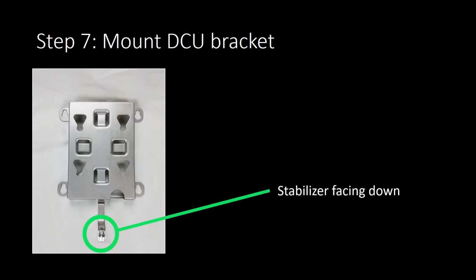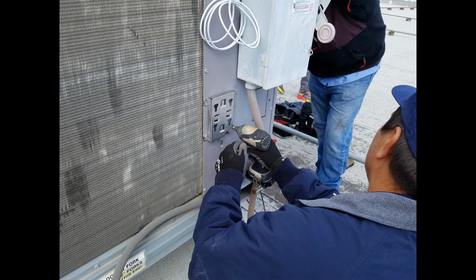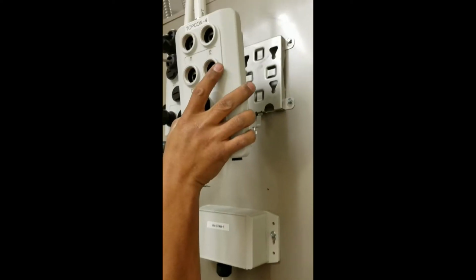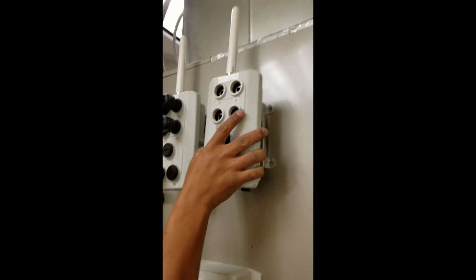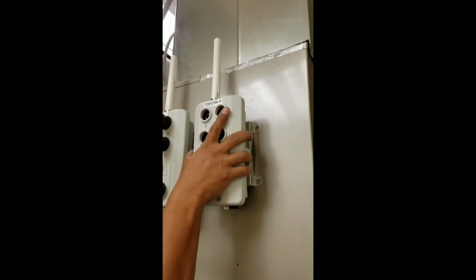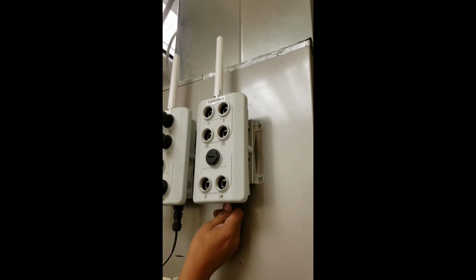After the sensors have been installed, it is time to install the data collection unit bracket. Find the location that you marked in Step 3. Use the provided self-tapping screws to fasten the bracket to the exterior of the HVAC unit. Step 8. Install the data collection unit. Slide the DCU onto the mounting bracket and fasten the attachment screw.